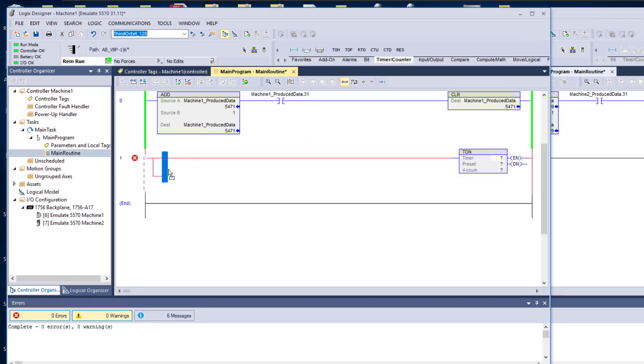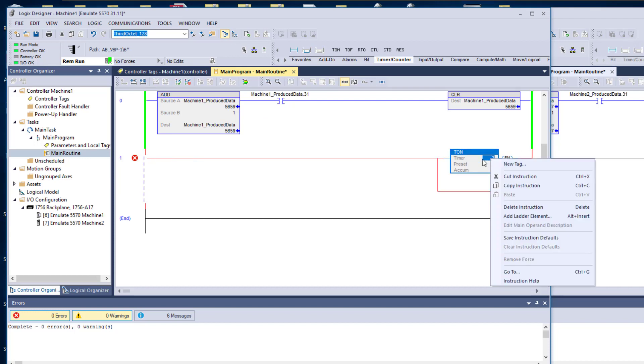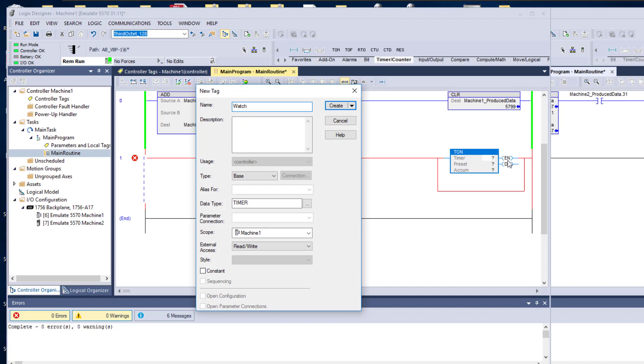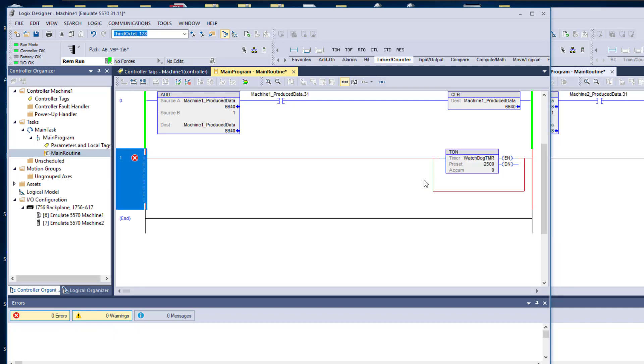Now that we have that set up, we can actually do a watchdog. We can do a standard timer, so we'll add another rung and add a timer. We're going to call this, in this processor, Watchdog Timer. Generally between two processors you want to keep it around two and a half seconds, maybe more if you have a bigger processor. I'm going from emulate to emulate on the same PC, so I can go a little bit smaller, but let's just do a base implementation of two and a half seconds.